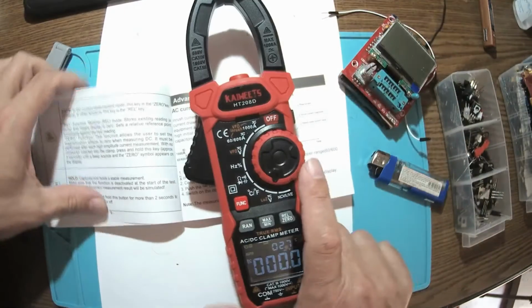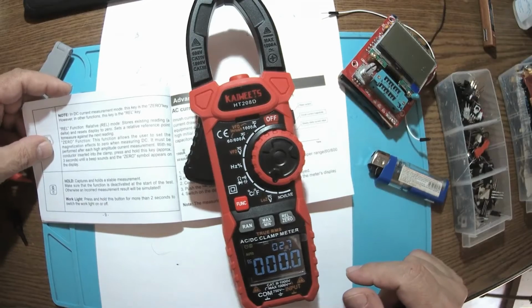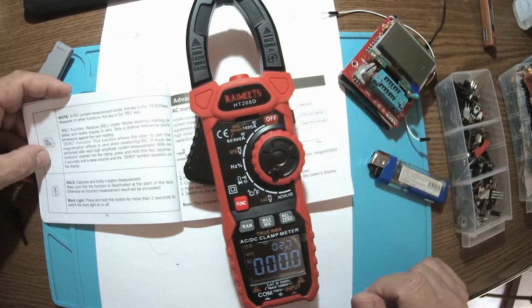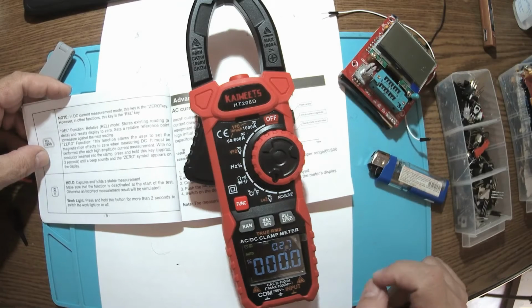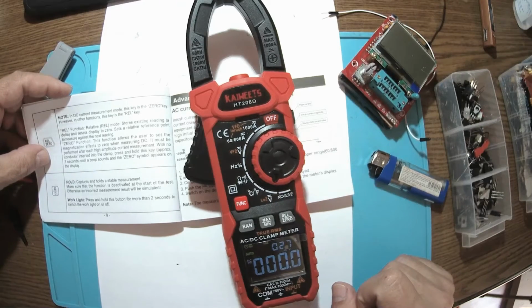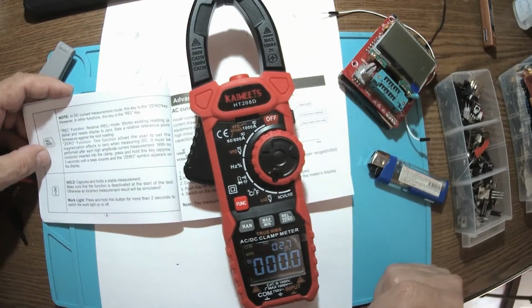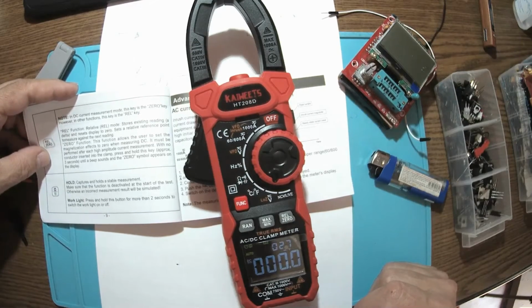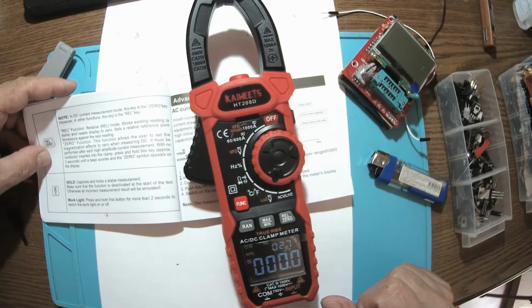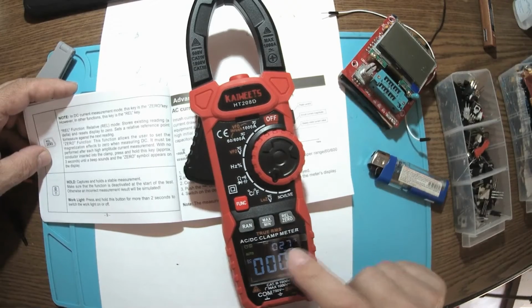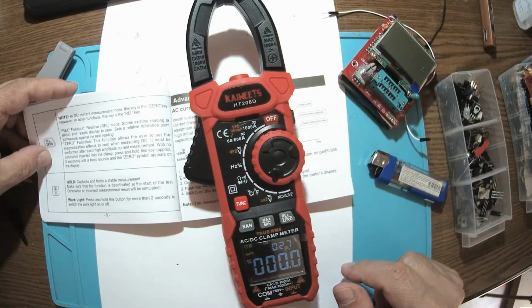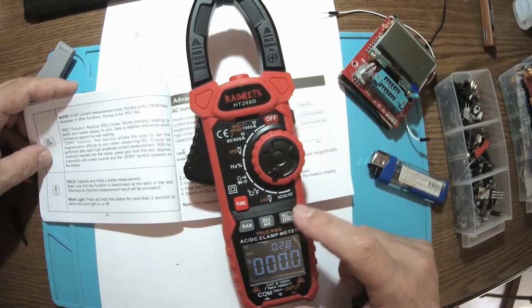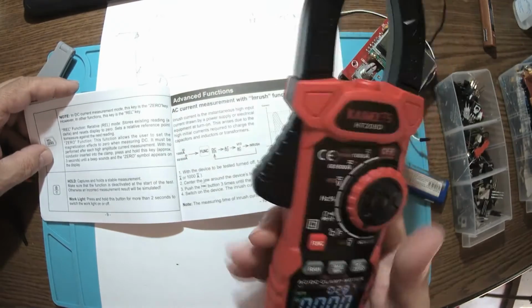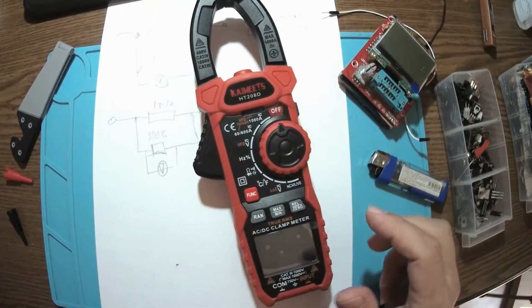And also something interesting here. In DC current measurement mode, this key turns the clamp meter to 0. That means it allows the user to set the magnetization effect to 0 when measuring DC, this magnetization effect in here. Okay, that's very interesting. So it's a kind of calibration, zero calibration, let's call it. And that's only for DC current measurement. In all the other measurements, this button here has a relative mode. Auto or relative.